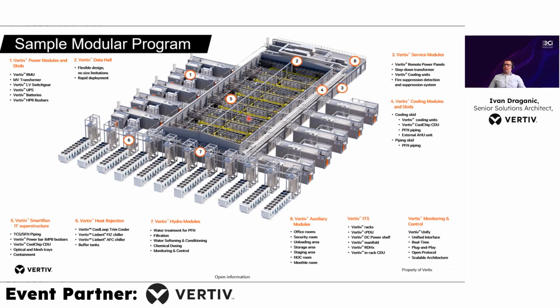The white space is filled with what we call SmartRun, and the SmartRun is a prefabricated infrastructure that houses the critical power for the GPUs and for the other IT equipment, and the liquid cooling secondary fluid network infrastructure as well. It's built on steel skids that are either self-supported, mounted on the floor, or can be mounted from the ceiling. It can be a combination of both if needed. On that steel construction, we install the critical infrastructure. And it's already prepared for the NVIDIA requirements, like the distributed redundant topology with the bus bars for the 4 to make 3, and then the liquid cooling topology with all the branch offs and all the things that need to be there for the liquid cooling system to properly operate.